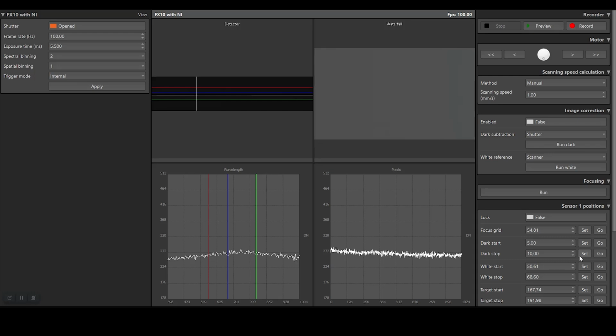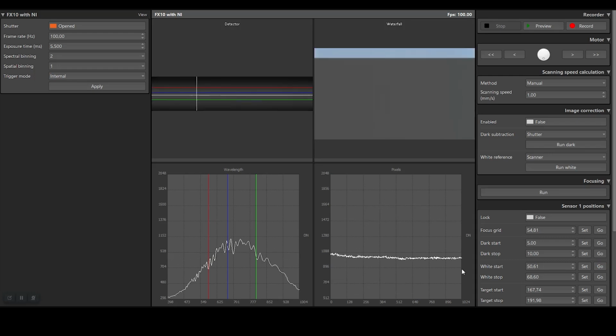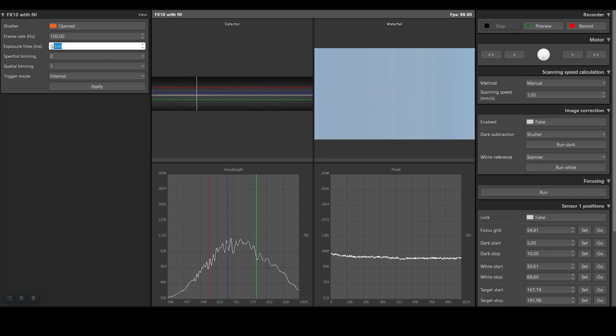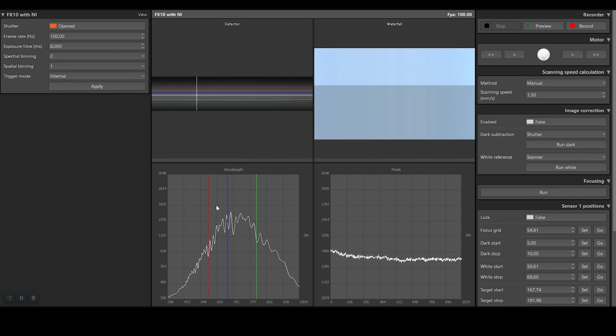Just to show you, so here again, I would have the white reference. We go again over there. So we see that here with this lens, we may need to increase the integration time. So for instance, here, I will put it around 8 milliseconds. It could be even more, but then I will have to have a much slower frame rate. So for example, if I put here 75 frames per second, I can put here something like 12 milliseconds.